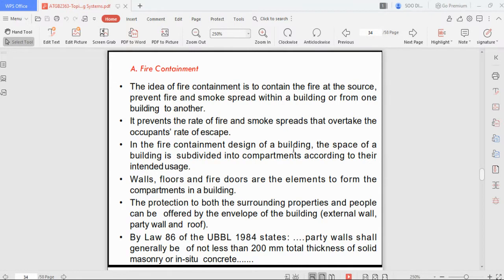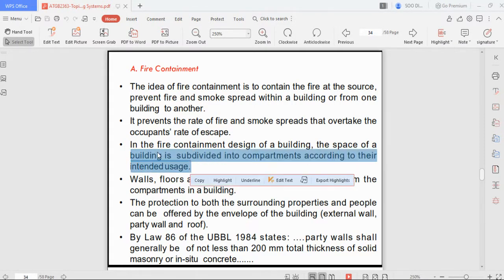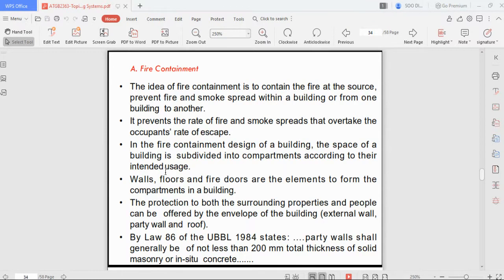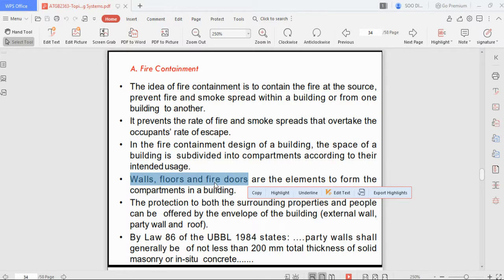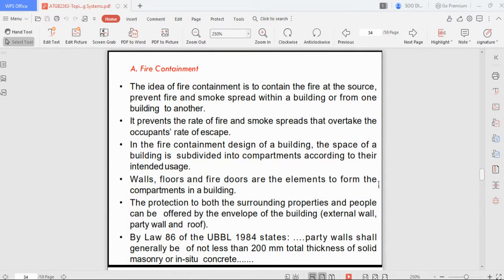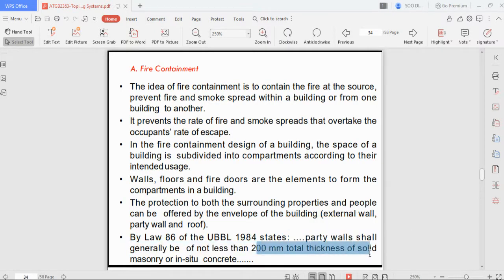Fire containment prevents the rate of fire and smoke spread from overtaking the occupant escape rate. The building space is subdivided into compartments according to intended use. When fire occurs in one compartment it spreads only within that area until it burns through the fire protection systems — walls, floor, or fire door — before spreading to other areas. The UBBL requires party walls to be not less than 200 mm total thickness of solid masonry or in-situ concrete.